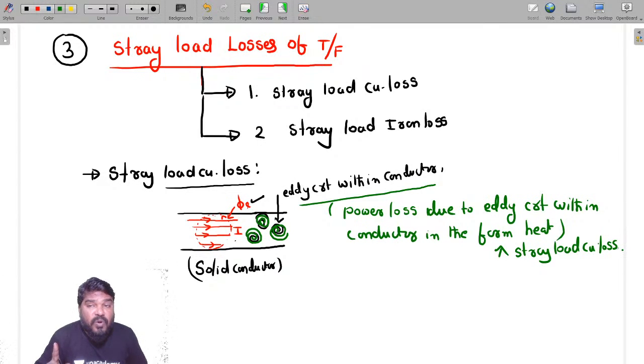So stray load copper losses means additional I square R loss. This is sometimes also called additional I square R loss present in the conductor due to leakage flux. This is the main reason for the stray load copper loss. Whenever leakage flux links with the conductor, an EMF is induced, which in turn produces a circulating current. The power loss in the form of heat due to this circulating current is known as the stray load copper losses.